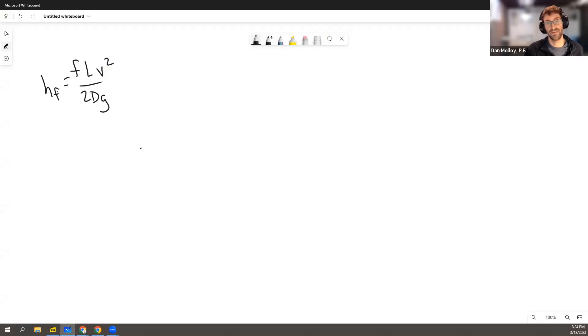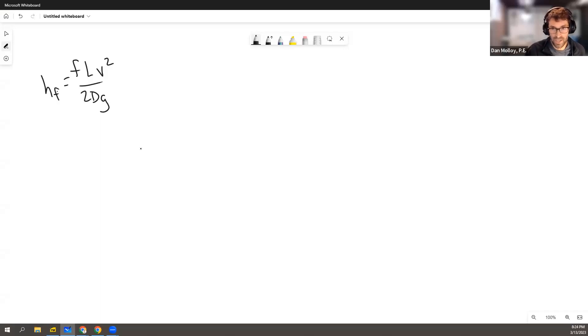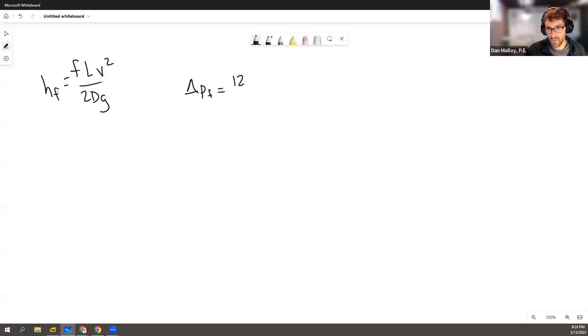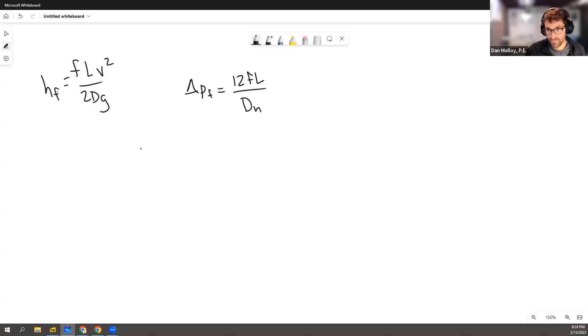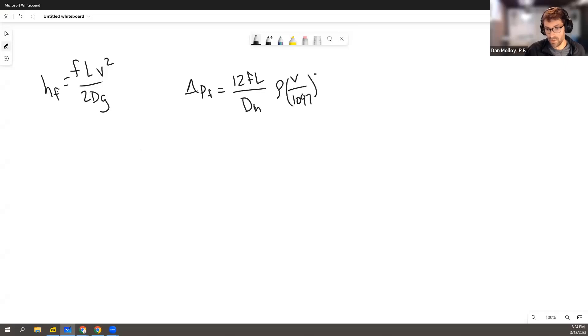Instead of HF, which usually comes out in feet when we use the standard Darcy equation, this one is given as delta P sub F equals 12FL over D sub H, the hydraulic diameter, times rho velocity over 1097 squared.